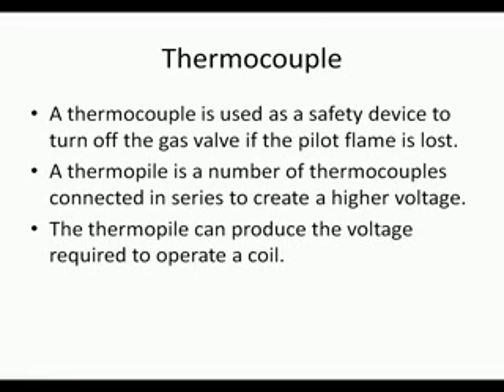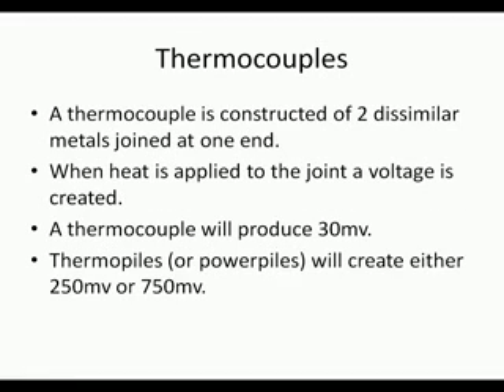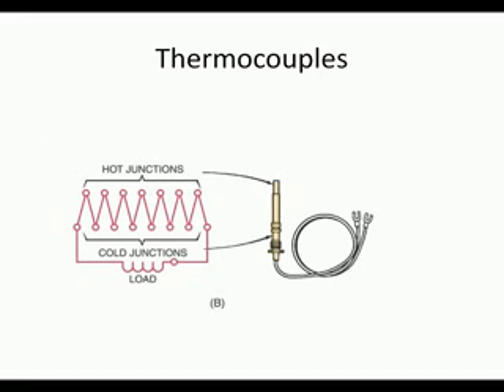During this lesson, we want to talk about gas ignition systems. First, though, we have to talk about a few safety devices. A thermocouple is used as a safety device to turn off the gas valve if the pilot flame is lost. A thermopile is a number of thermocouples connected in series to create a higher voltage. The thermopile can produce the voltage required to operate a coil.